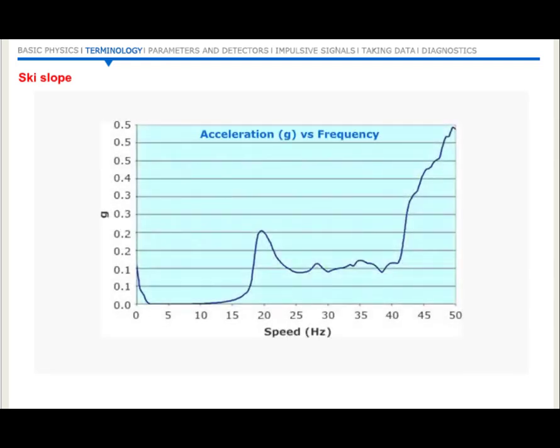If a high amplitude of vibration velocity at low frequency is observed, then the most common reason is an amplification of the data caused by the process of integration from acceleration to velocity. The spectrum shown here depicts the vibration acceleration as measured directly by the accelerometer sensor. To convert the spectrum from g versus frequency to millimeters per second versus frequency, we divide each value of g in the spectrum by 2 times pi times f as explained earlier.